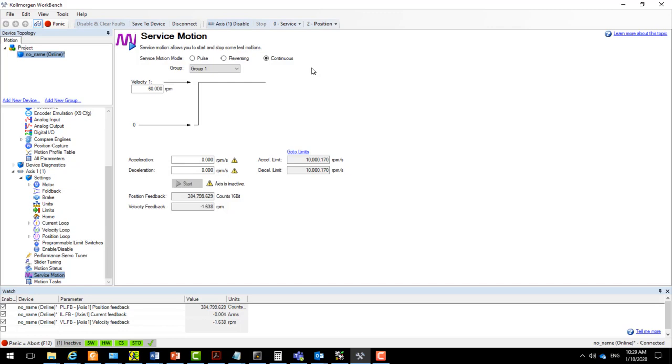But in general, most applications that use the AKD Home, AKD Jog, and AKD Move add-on instructions have the drive set up for service position, which is assumed for this test. Other command sources and drive operation modes will be covered at a later time. Also note that the command source 1 field bus does not apply to Ethernet IP except in the rare case of using the AKD torque move add-on instruction that requires the drive to be in torque mode.